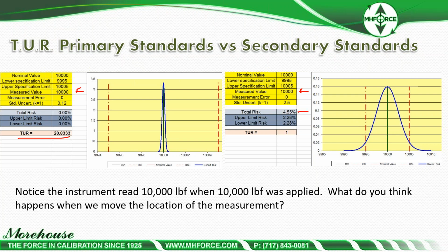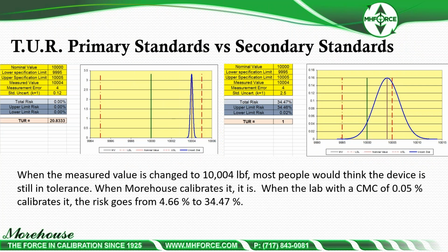Guess what? In this scenario, when we take measurement uncertainty into account, our total risk is 4.55%. Our upper and lower are each above 2. Can we make a statement of conformance, a statement of compliance, a pass-fail? Can we do any of that if my risk is over 2%? Probably not. And furthermore, what happens if we move that? So both were at nominal. If we move it to 10,004, the lab with the low uncertainty calibrates it. They can still say your device was in tolerance, which prevents you from doing mass recalls. Whereas the other lab can't make that claim. The risk goes from 4.66 to 34.7. They have to call it out of tolerance.